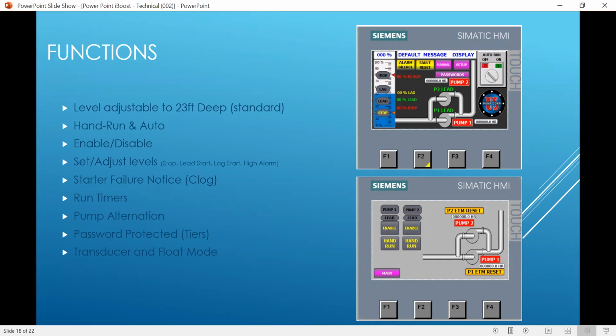On your clogs, just one more note. Sometimes it's a 5-second deal. I mean, it's just something got jammed up in there, and it's just trying to suck through the pump itself. When the fault goes out and the pump stops, now whatever that piece of debris is falls out, and then you go hit your reset and you're back in business. So we feel that there's just a lot of conveniences.